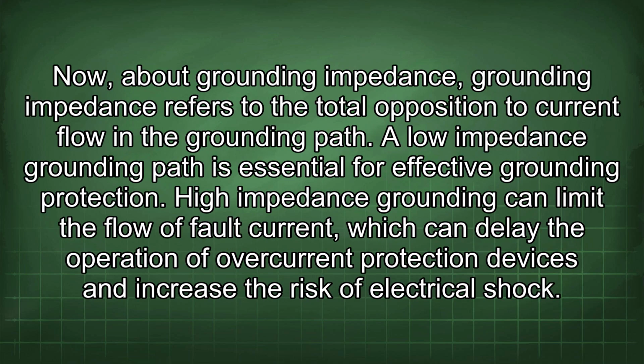Now, about grounding impedance. Grounding impedance refers to the total opposition to current flow in the grounding path. A low impedance grounding path is essential for effective grounding protection. High impedance grounding can limit the flow of fault current, which can delay the operation of overcurrent protection devices and increase the risk of electrical shock.